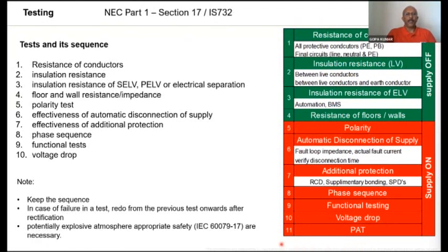Say, for example, there is an apartment, and the electrical wiring is very well done, completely done. I will give an example. One of the leading builders in Bombay is implementing this for their high-rise buildings. The wiring is perfect, but now the builder is also giving a service to the apartment owners. They provide two PAT testing instruments. Two PAT meters are kept in the common facility or the electrician's facility. So when a newcomer or a new owner occupies the building, the electrician goes there and tests all his equipment with the PAT tester.